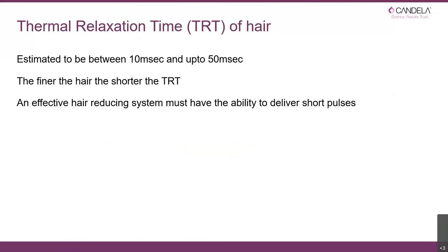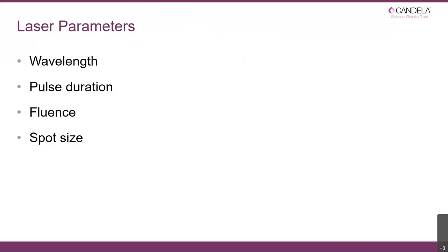Various studies come up with different numbers, but the estimate of the TRT of hair is between 10 and 50 milliseconds. The difference in TRT time is based on the thickness of the hair — the finer the hair, the shorter the thermal relaxation time, because the volume of hair being heated is smaller with thin hair than with thicker hair. So an effective hair reducing system must have the ability to deliver short pulses.